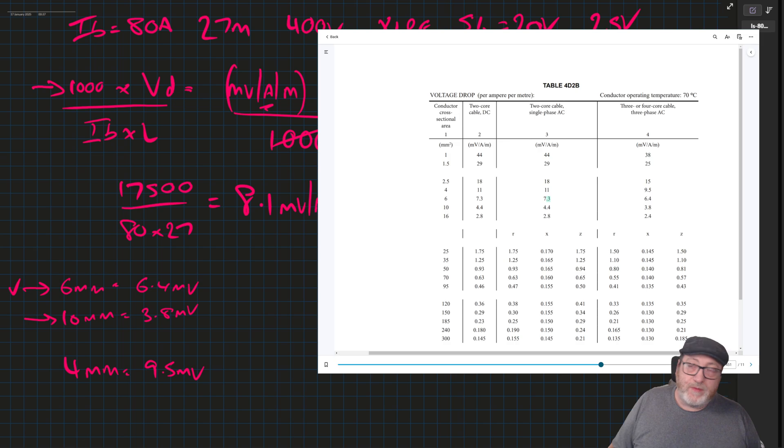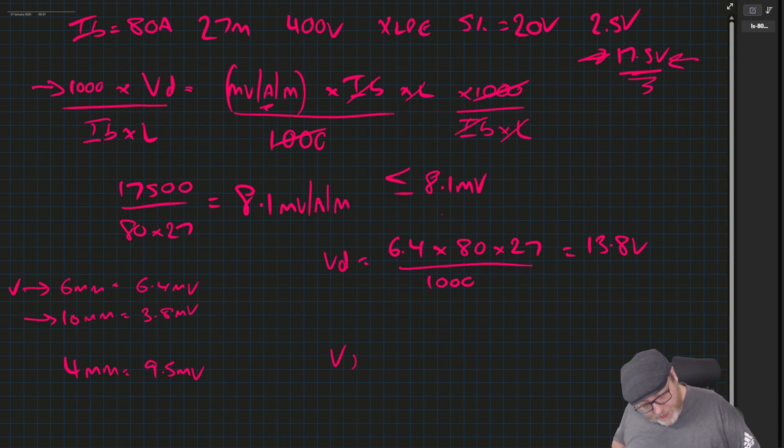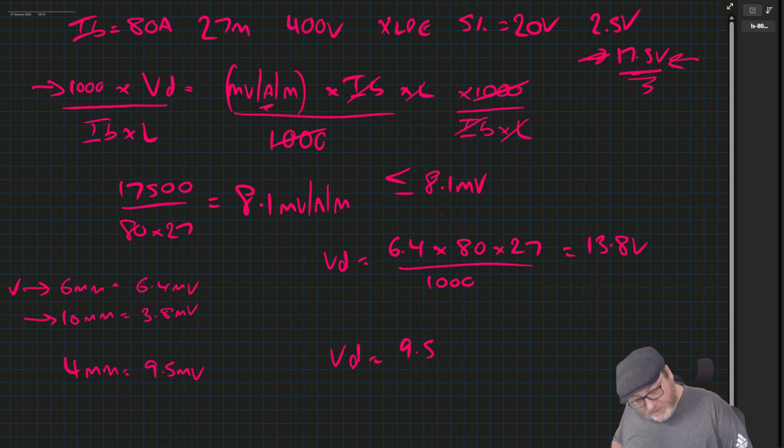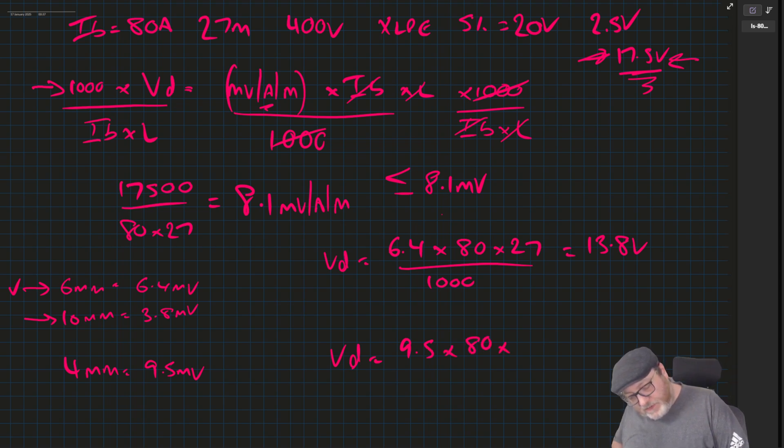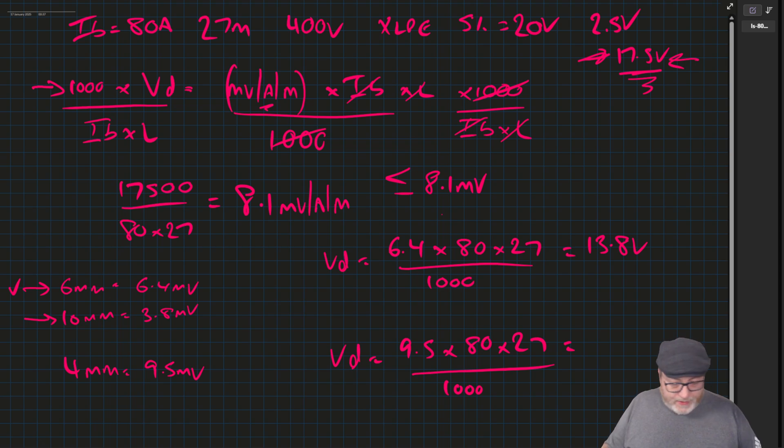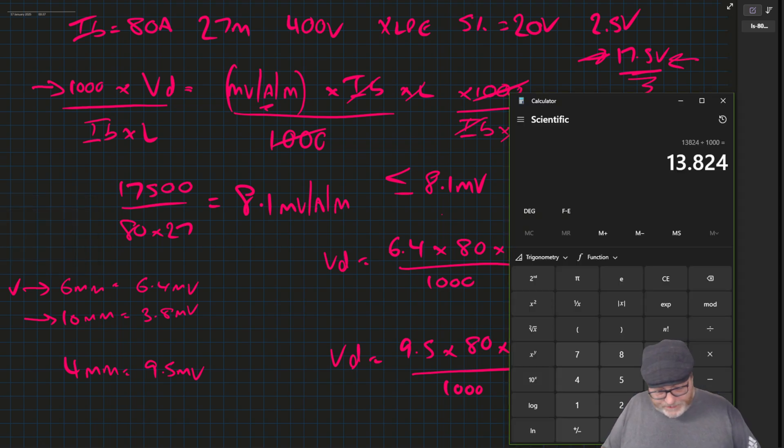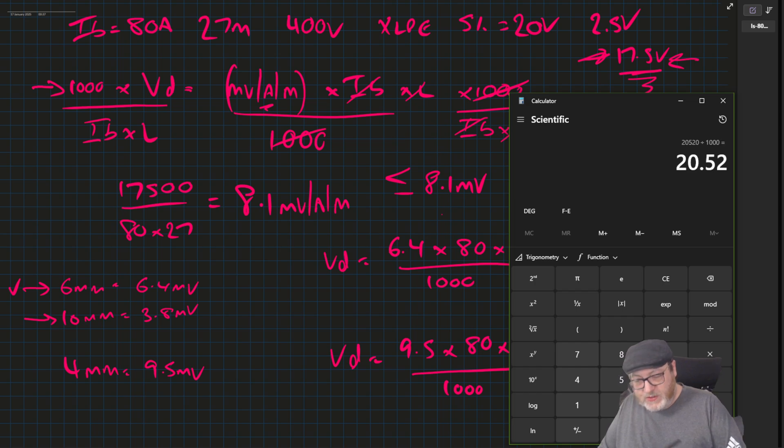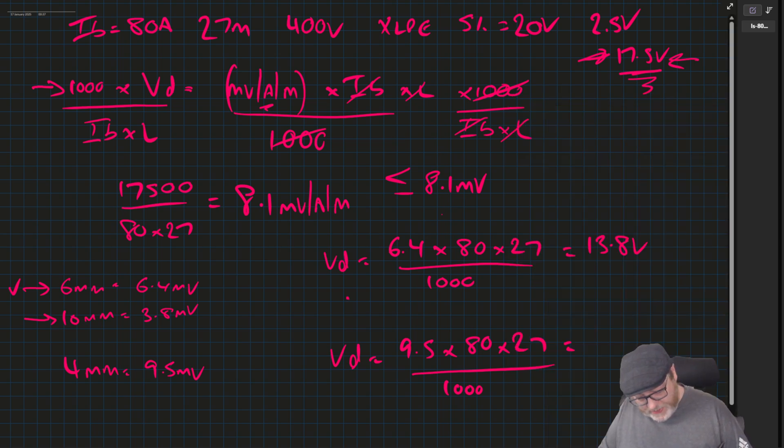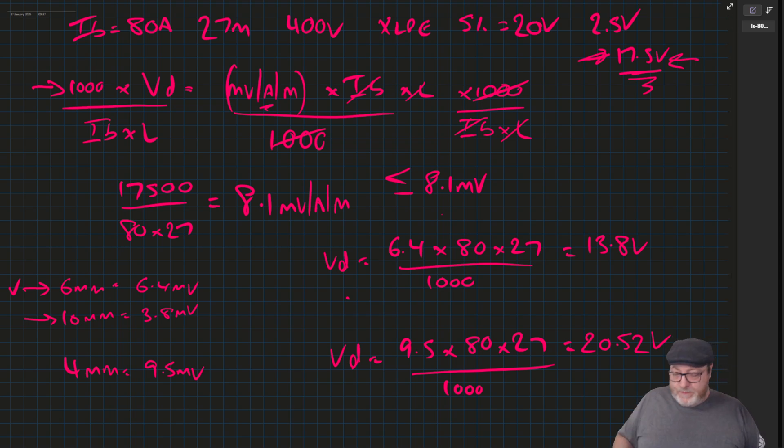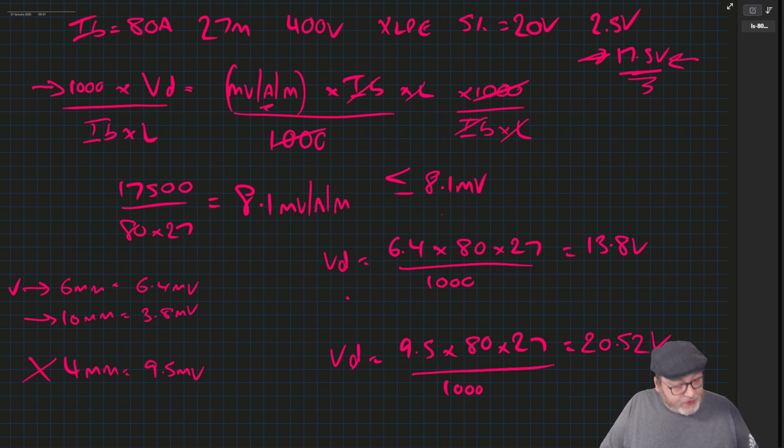So technically, we can work this out and it should be that we proved the 4 mill to be too small. So volt drop equals 9.5 millivolts times 80 times 27 over 1000 equals 9.5 times 80 times 27 over 1000, 20.52 volts. So what we've done here is we've proven that the 4 mill is definitely too small.